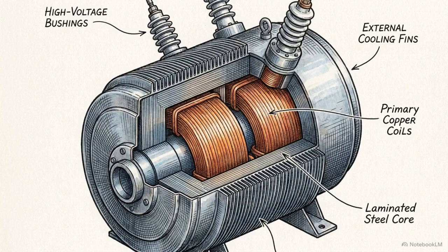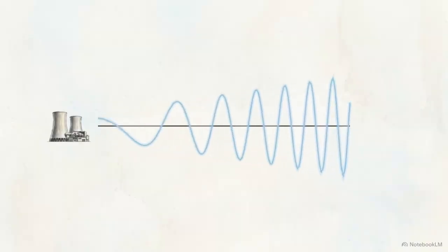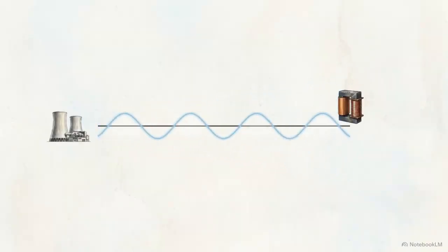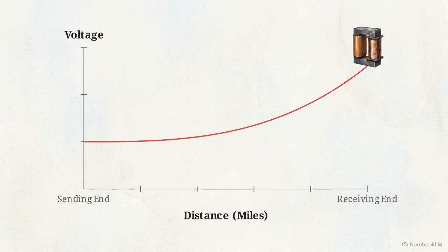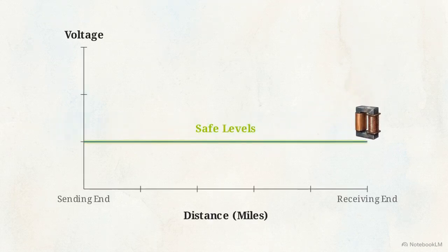To counteract the Ferranti effect, engineers rely on specific hardware known as shunt reactors. A shunt reactor acts as a giant inductive sponge clamped onto the line, designed to absorb excess energy. Returning to our chart, connecting the reactor neutralizes the slosh and pulls the rising voltage back down to safe levels.